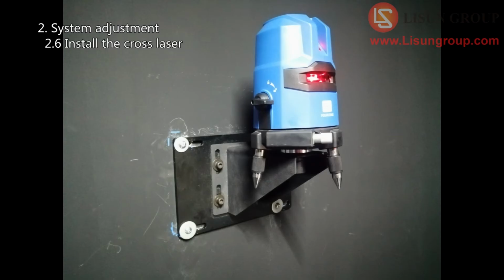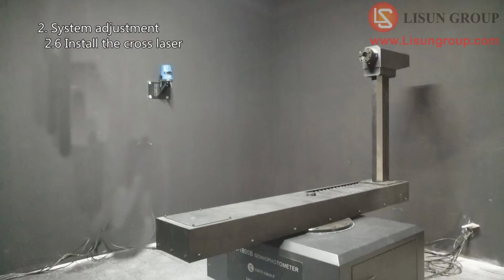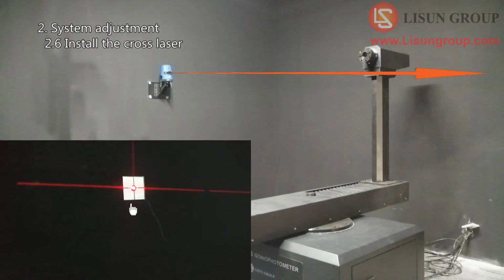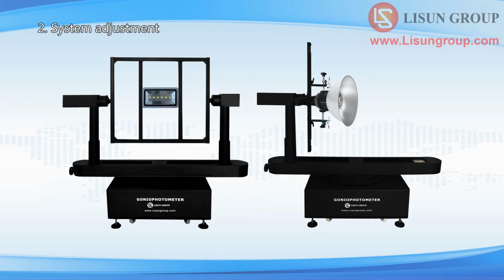Use screws to fix the support to the wall after the adjustment. You may need to fine-tune the position of cross laser to make sure that it is still in correct direction. All the screws should be tightened after the adjustment. Rotate the gamma angle back to 0 degree position. The cross laser beam hit the opposite wall. Make a permanent mark here. The installation and adjustment are finished.